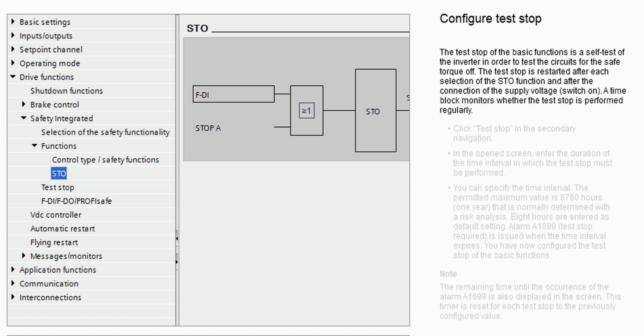The test stop of the basic functions is a self-test of the inverter in order to test the circuits for the Safe Torque Off. The test stop is restarted after each selection of the STO function and after the connection of the supply voltage switch on. A time block monitors whether the test stop is performed regularly. Click Test Stop in the secondary navigation.